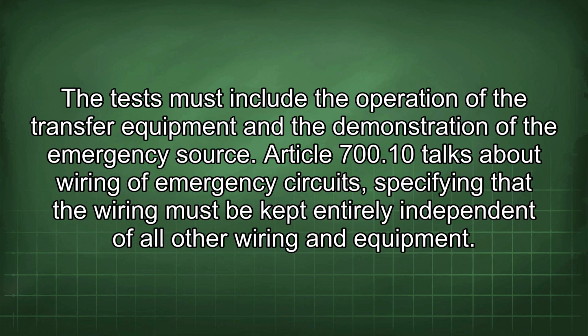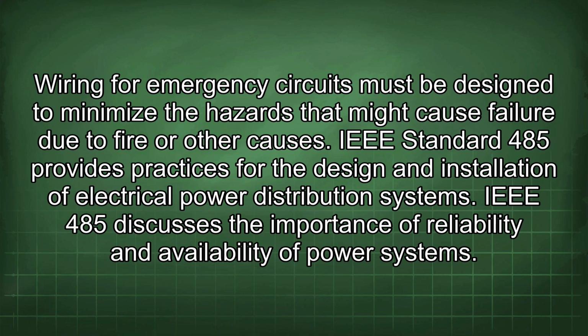Article 700.10 talks about wiring of emergency circuits, specifying that the wiring must be kept entirely independent of all other wiring and equipment. Wiring for emergency circuits must be designed to minimize the hazards that might cause failure due to fire or other causes.